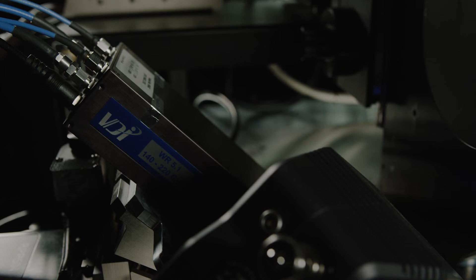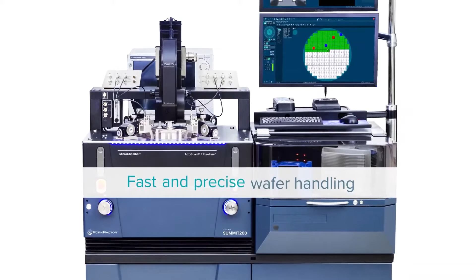And then Dominion Microprobes broadband probes, they combine the coaxial and the waveguide signals all the way to the probe tips with an internal diplexer. And then last but not least, of course, all the FormFactor probe stations that come in many different flavors, 200 millimeter, 300 millimeter probe station, semi-automated, fully automated. And along with that, of course, you need to have measurement over temperature capabilities with thermal systems that we do provide, Contact Intelligence Technologies, which is a patented technology to enable calibration monitoring and recalibration, unattended use, and reduce soak times. Autonomous RF capabilities, we talked about that. Modularity probe arms to allow an easy band swap between different probe arms. And also, of course, ISS standards to perform calibration, and software to perform calibration tasks and post-processing tasks as well.